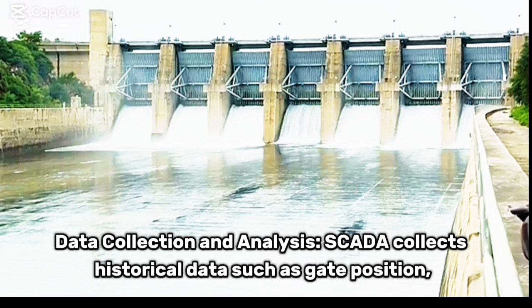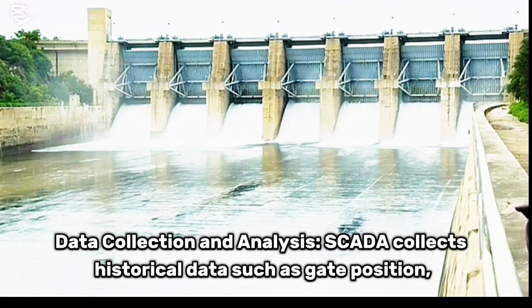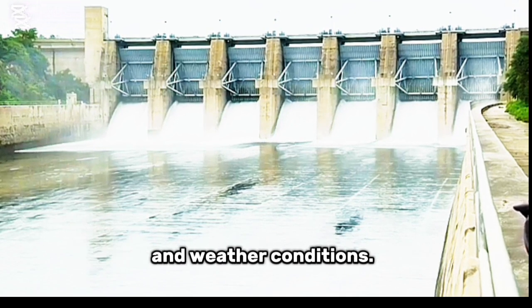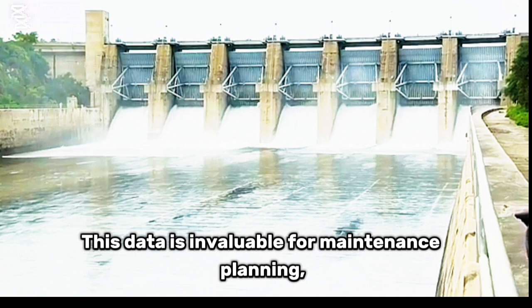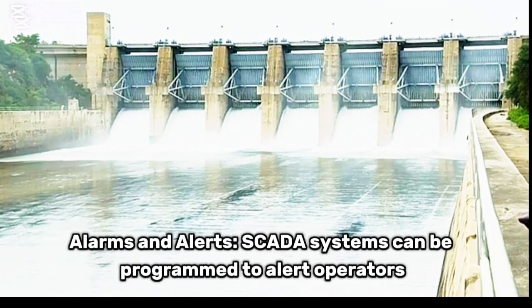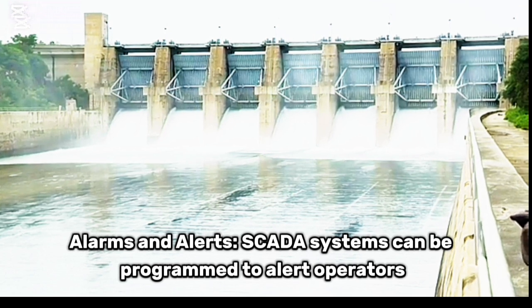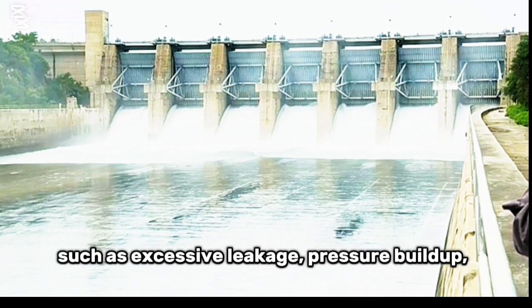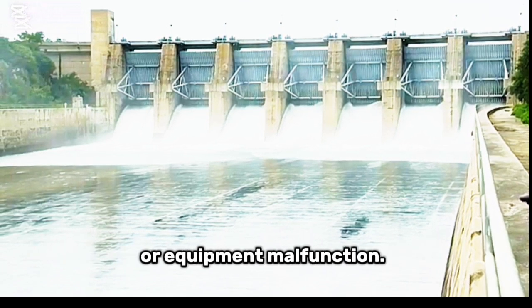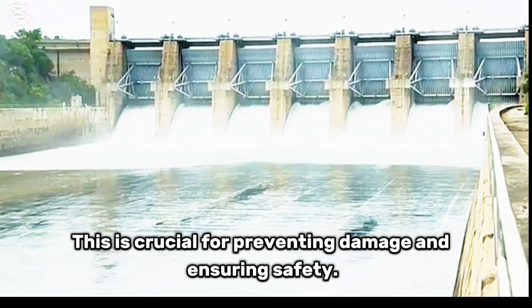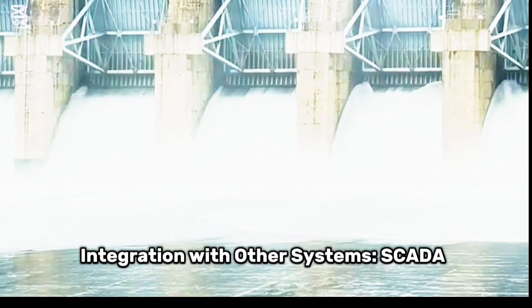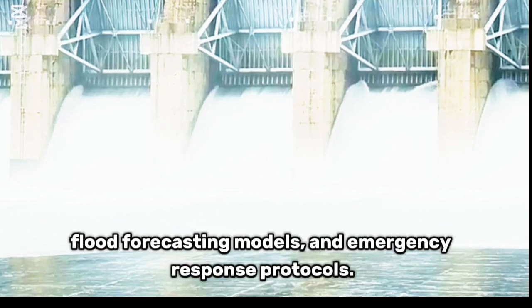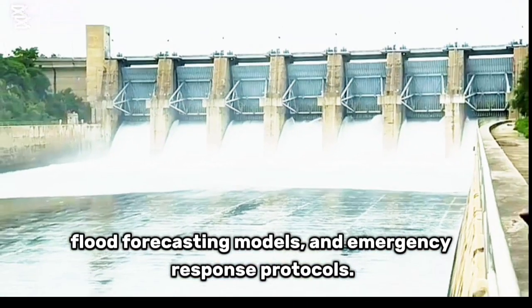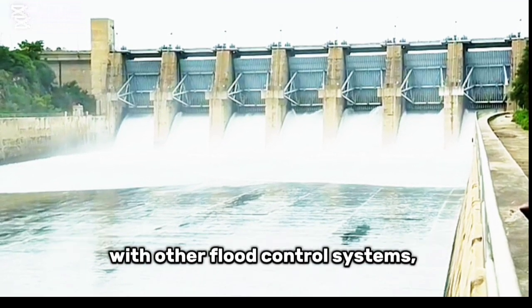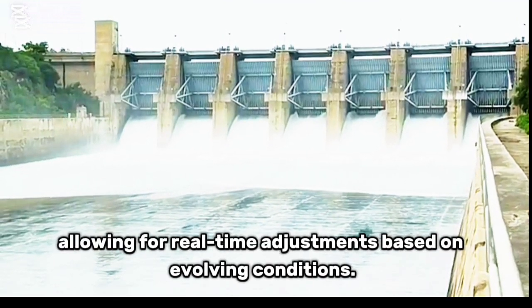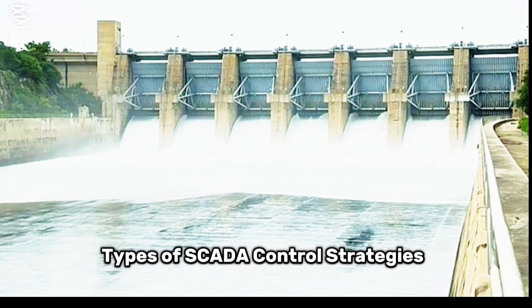Data collection and analysis. SCADA collects historical data such as gate position, operational cycles, hydraulic pressures, and weather conditions. This data is invaluable for maintenance planning, troubleshooting, and predictive analysis. Alarms and alerts. SCADA systems can be programmed to alert operators if certain thresholds are exceeded, such as excessive leakage, pressure buildup, or equipment malfunction. This is crucial for preventing damage and ensuring safety. Integration with other systems. SCADA can be integrated with weather monitoring systems, flood forecasting models, and emergency response protocols. This integration ensures that gates operate in harmony with other flood control systems, allowing for real-time adjustments based on evolving conditions.